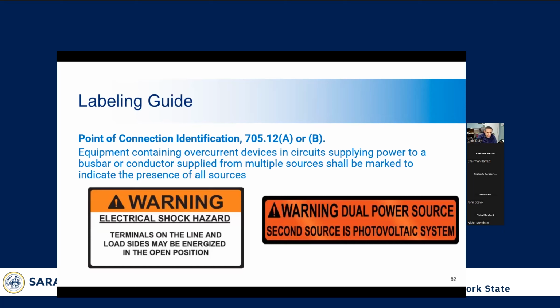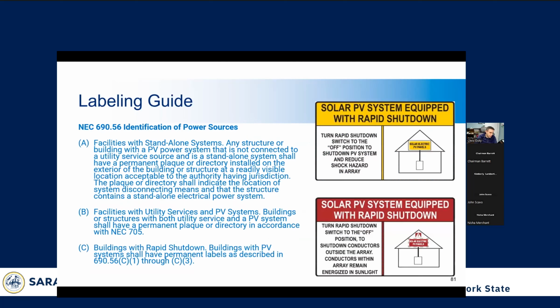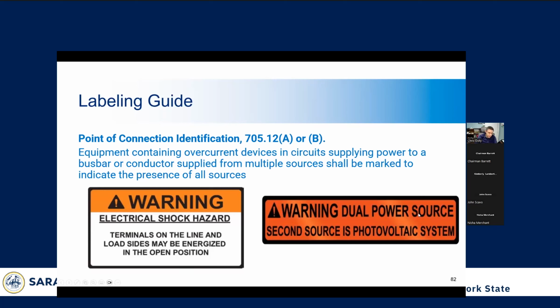So here we have the point of interconnection identification. This is a requirement, and it's to simply identify all sources of power supplied to a bus bar or a conductor. It allows someone to know that there's two power sources, and the second power source obviously is a PV system. You would also want to have some kind of way to tell them where the other source can be shut down. And this is important because it may be the first indication that PV is installed in a building. If the PV system is on the back of that building and the electrician comes in through the front, they may not even know that it's there.